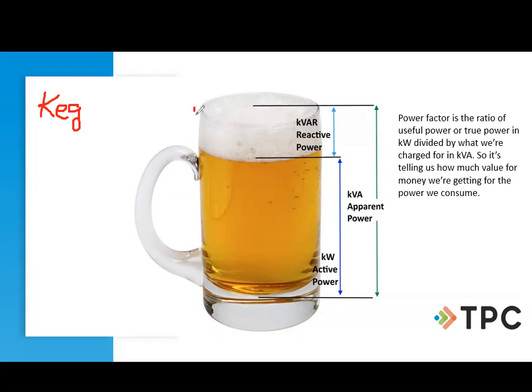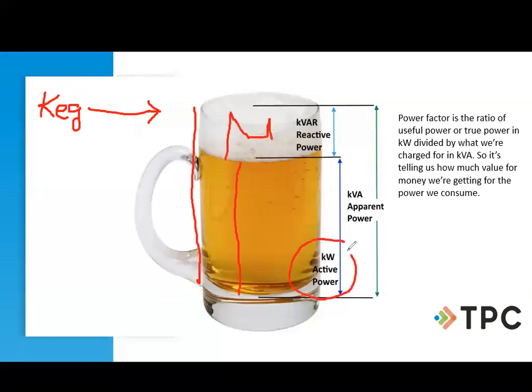Well, the keg has to produce all of this. But you can see from here up, that's not going to do much for us, that foam. And so the foam is just taking up space, basically. But the keg had to produce it, and that's it. But what's actually going to have an impact on us is the liquid part of it, right? So that would be compared to the kW. And so the kVA is everything that the keg produced. But our coils and capacitors would be reflected by the foam on top here.